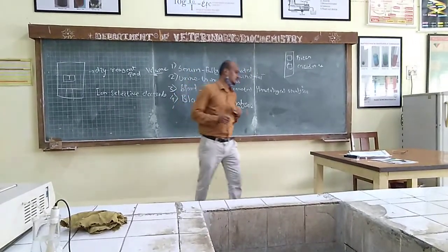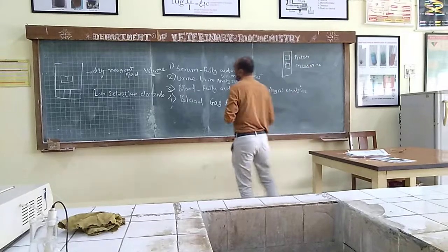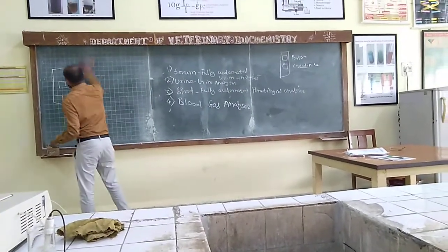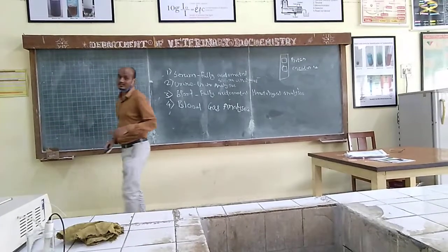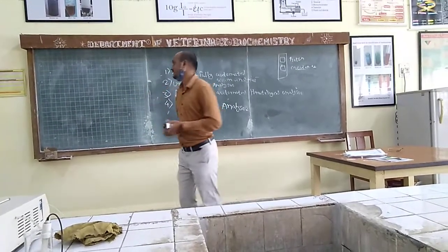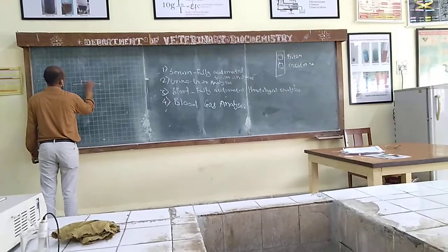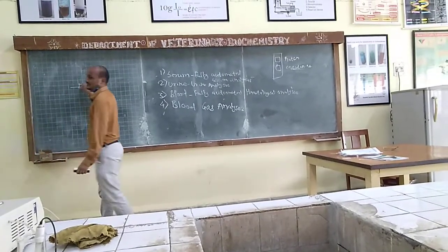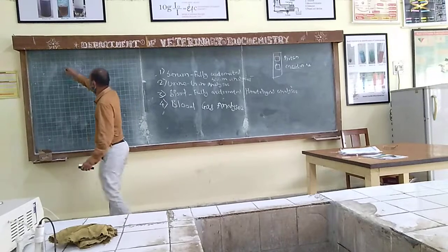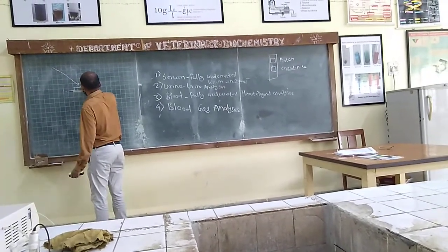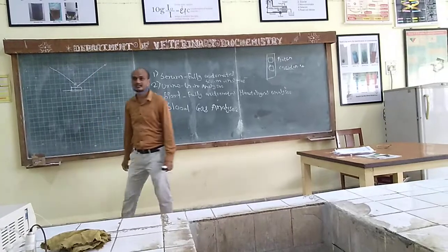The principle of this urine analysis is based on reflectance. Normally we talk about absorption, but here it is based on reflectance. This is the analysis strip, for example, particularly for protein. We pass the light through here, and this light bounces back at another angle.